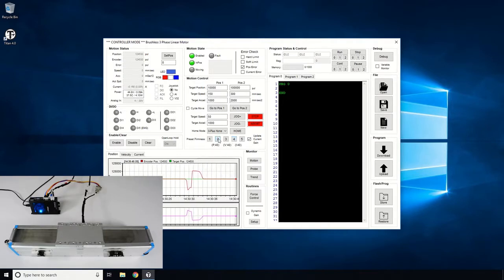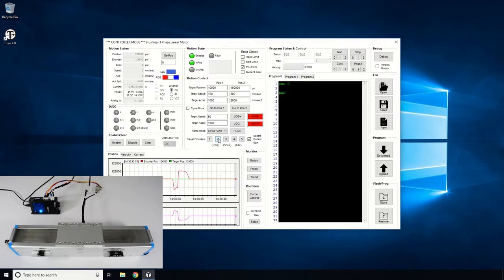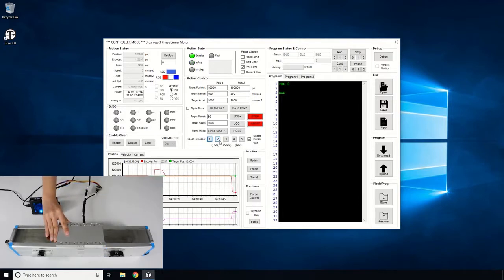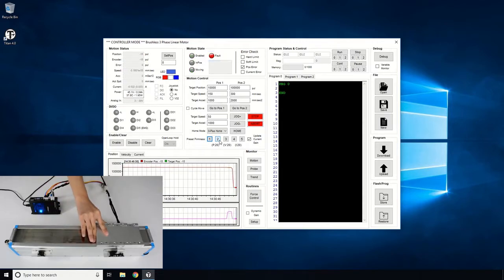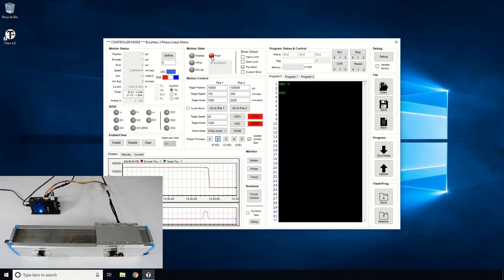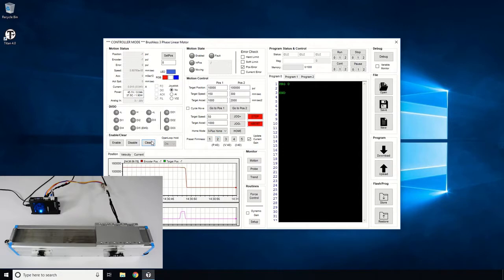Next, let's try to create a Position Error Fault. Push the motor so that the error range is above 1000 counts for more than 1 second. The motor should fault and the motor disables. Double-click on the Fault Indicator to find out what type of fault it is. Clear the fault and enable the motor again to continue with the Motion Test.